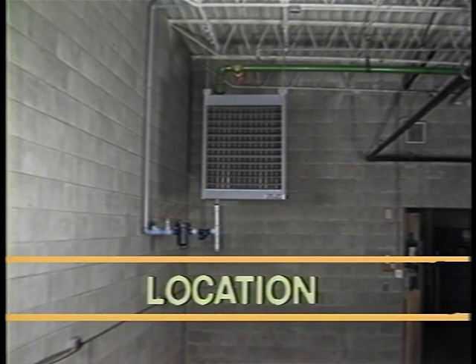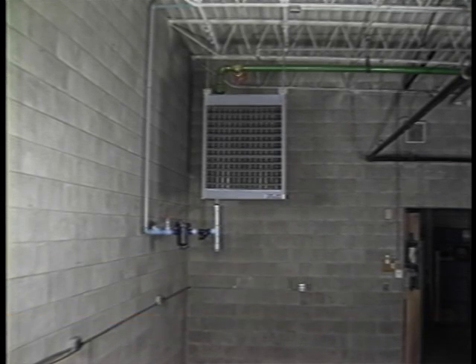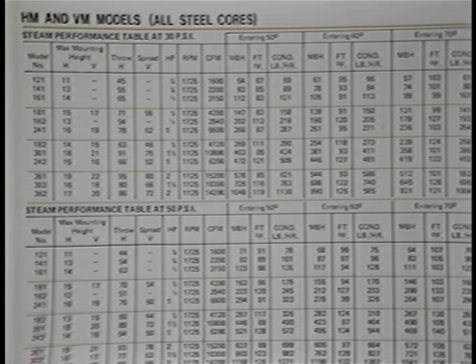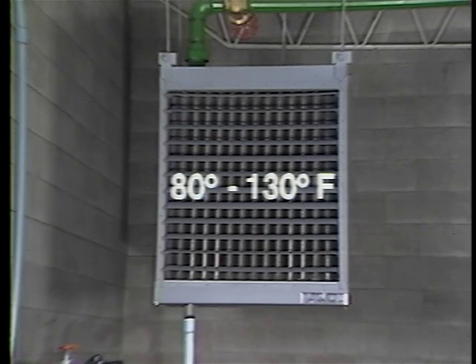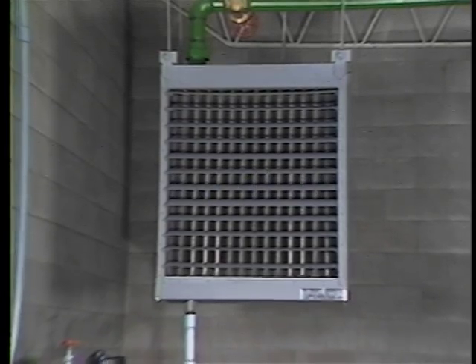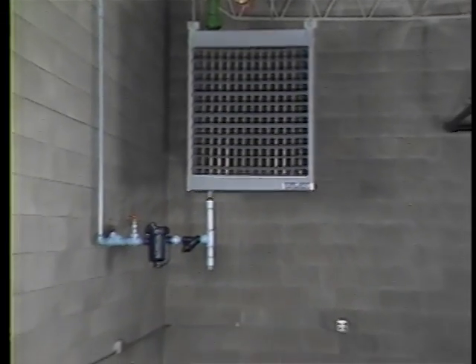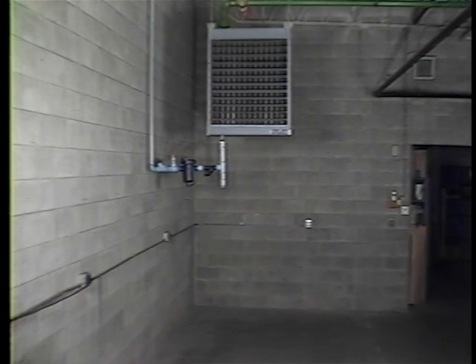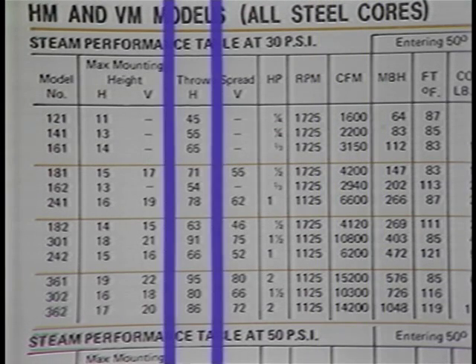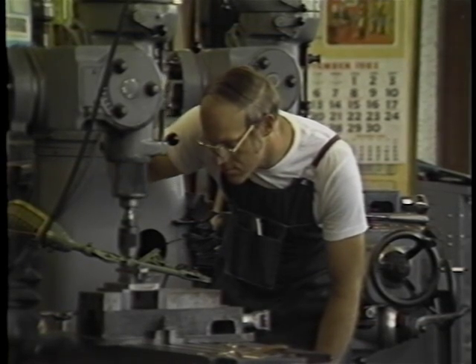How the unit is installed can have a bearing on its efficiency and service life. The mounting height of a unit heater is determined by the physical restrictions of the space it heats. The CFM of the fan and the heater's final air outlet temperature are then selected to conform to the area's needs and limitations. The air outlet temperature should be between 80 and 130 degrees Fahrenheit. The higher the air outlet temperature, the more buoyant the air and the more difficult it becomes to force the air down to the area to be heated. Increasing the CFM of the fan lengthens the effective throw — the distance the air will travel — but may produce an objectionable evaporative cooling effect on workers.